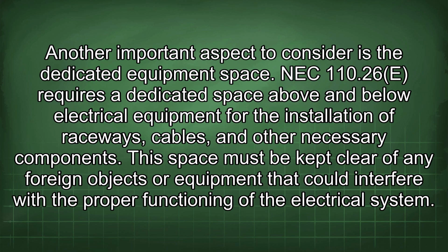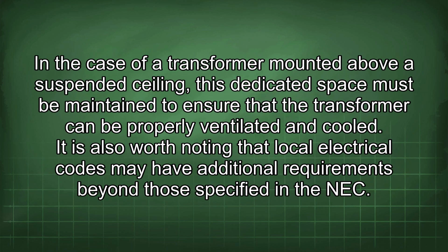Another important aspect to consider is the dedicated equipment space. NEC 110.26 requires a dedicated space above and below electrical equipment for the installation of raceways, cables, and other necessary components. This space must be kept clear of any foreign objects or equipment that could interfere with the proper functioning of the electrical system. In the case of a transformer mounted above a suspended ceiling, this dedicated space must be maintained to ensure that the transformer can be properly ventilated and cooled.